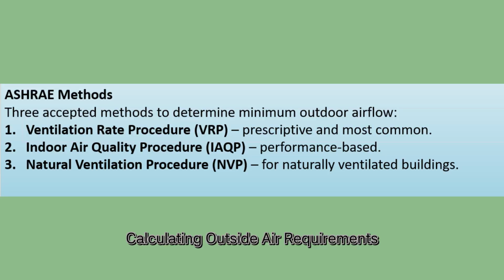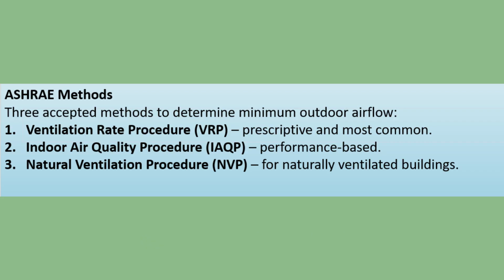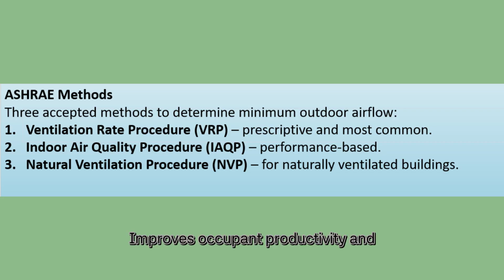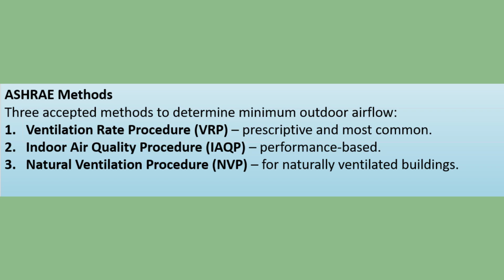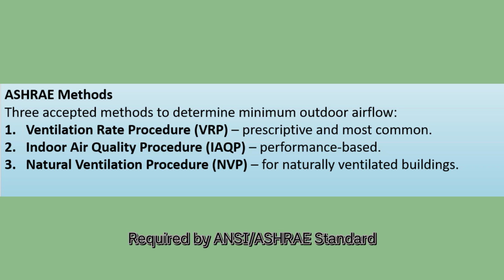Calculating outside air requirements. The purpose of outdoor air is to supply fresh air to dilute indoor contaminants, CO2, allergens, VOCs. It improves occupant productivity and reduces absenteeism. Required by ANSI ASHRAE Standard 62.1, Ventilation for Acceptable Indoor Air Quality.